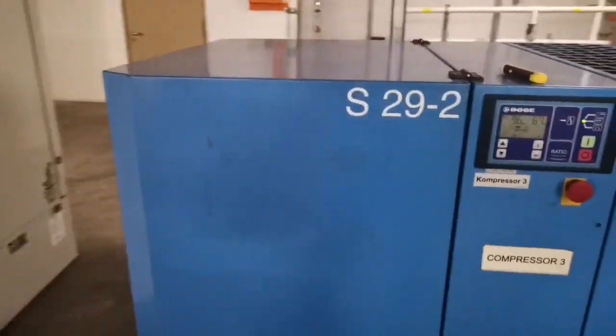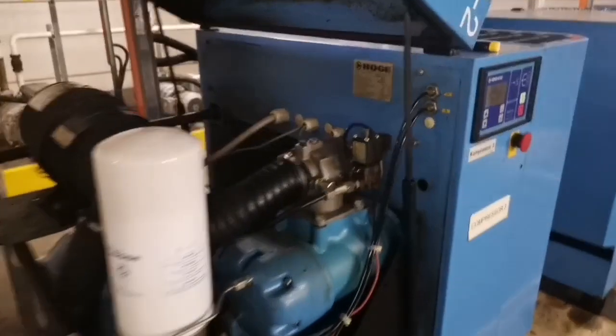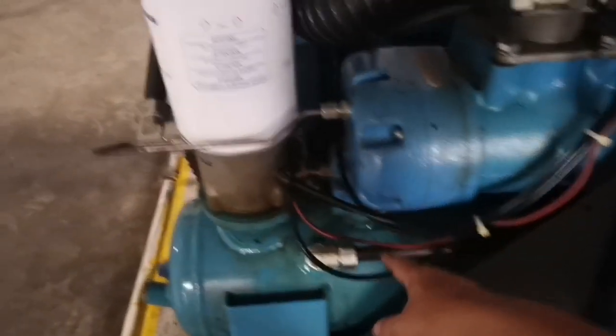Today, just a quick video about the BOGE compressor error 9. So for me, if I have an error 9, the first thing I would check is all the tubings — sometimes when they're broken and things like that, it wouldn't work and you get an error 9.